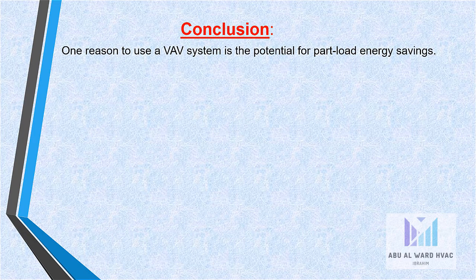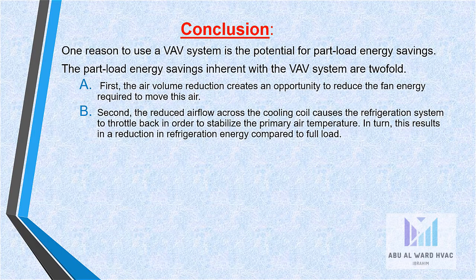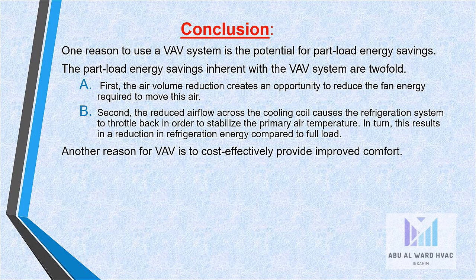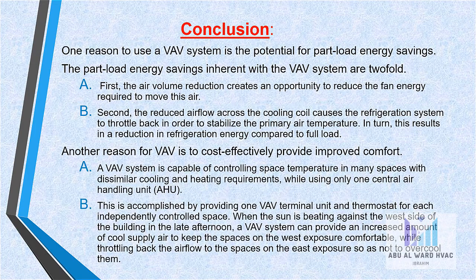One reason to use a VAV system is the potential for part load energy savings, which are twofold. First, the air volume reduction creates an opportunity to reduce the fan energy required to move air. Second, the reduced air flow across the cooling coil causes the refrigeration system to throttle back to stabilize the primary air temperature, resulting in a reduction in refrigeration energy compared to full load. Another reason is to cost-effectively provide improved comfort — a VAV system is capable of controlling space temperature in many spaces with dissimilar cooling and heating requirements while using only one central air handling unit.